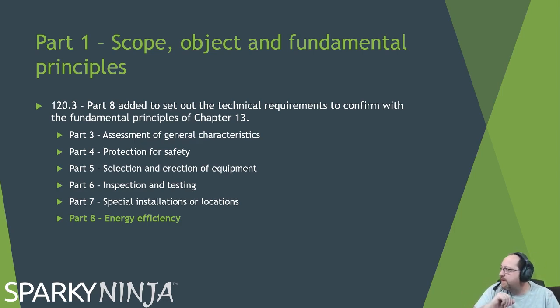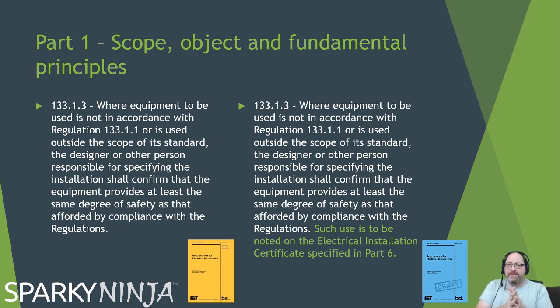I'm not sure how the points system works yet — I'll be looking into that and introducing it when we do a Part 8 section in this series. There is a Part 8, and because there's a Part 8, under 120.3 — the Fundamental Principles of Chapter 13 — it's now a requirement in the Fundamental Principles to comply with Part 8 as well. One other minor change in Part 1: Regulation 133.1.3 used to say that where equipment is used outside its standard, the designer shall confirm the equipment provides at least the same degree of safety. We've now got an additional sentence in the 18th which says such use is to be noted on the electrical installation certificate specified in Part 6 — it's all about documenting departures in your installation.